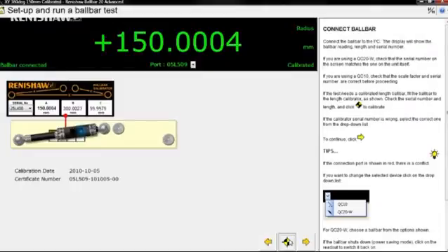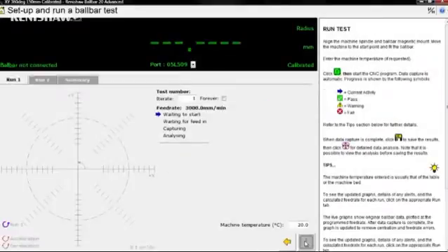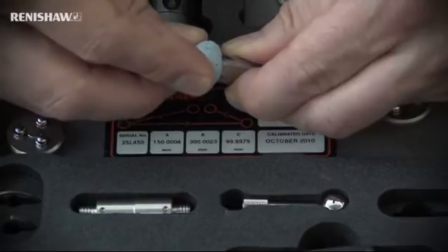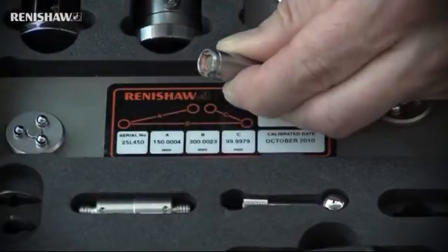Before proceeding to data capture, you need to make sure that the tool cups are clean and then attach them to the machine. Clean the cups by pressing them into the cleaning compound. This will remove any accumulated dirt or swarf from the magnets.